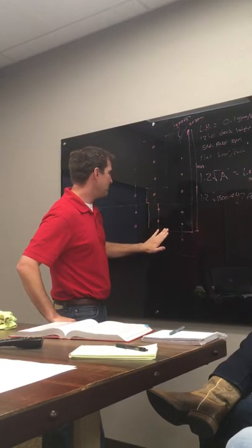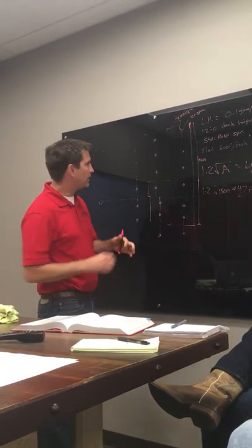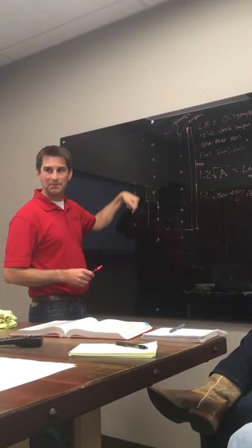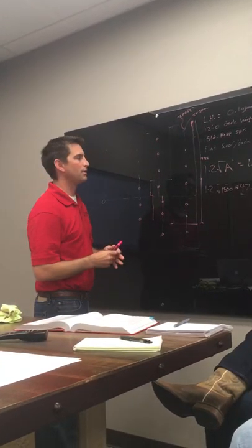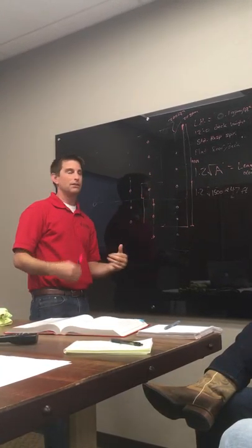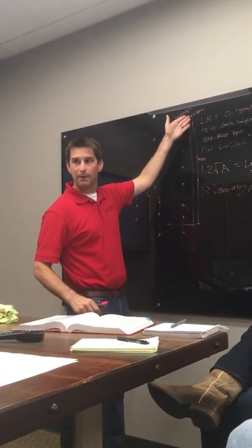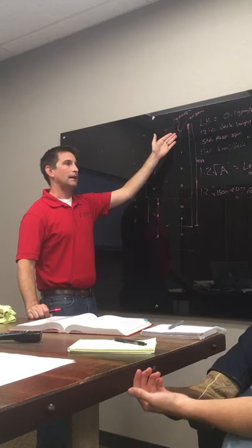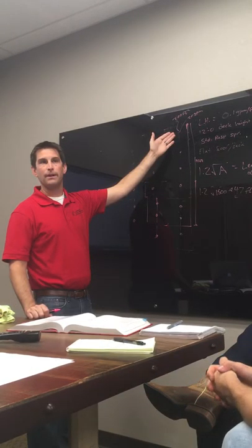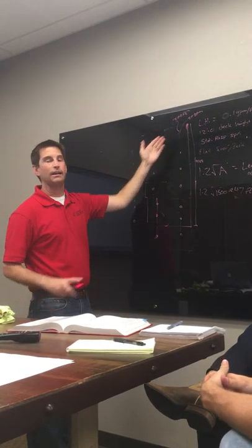Because so many people want to grab that end head and work their way in the opposite direction, because it's further, right? But you have to understand we're not doing a supply, we're doing a demand calc. So what we're saying is we need 20 GPM here. So in order to get 20 GPM here, let's say we need 11 PSI.